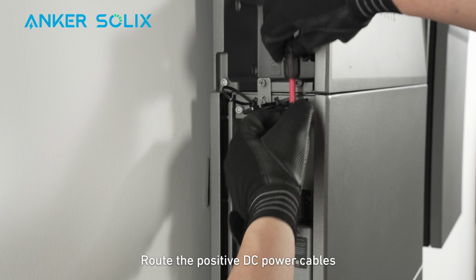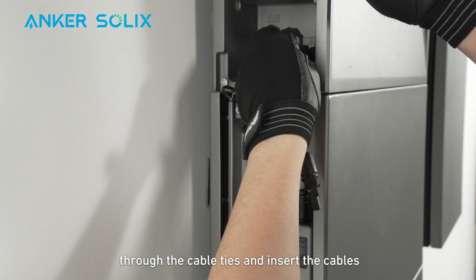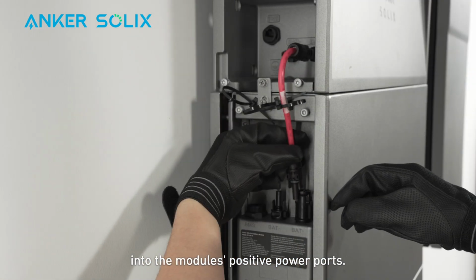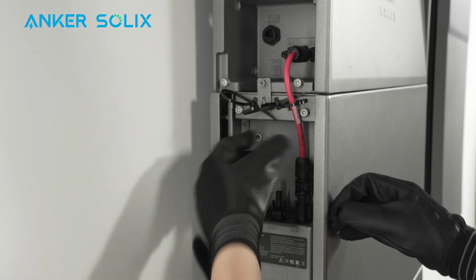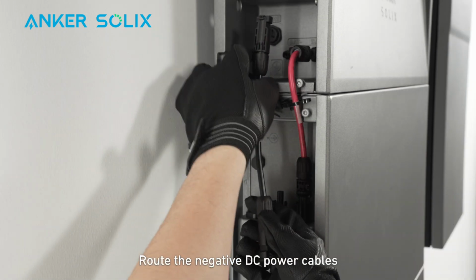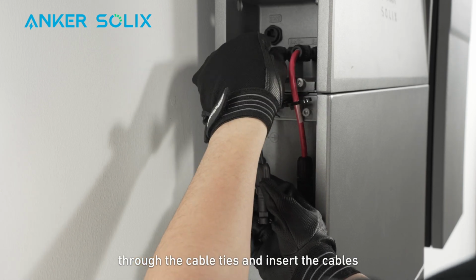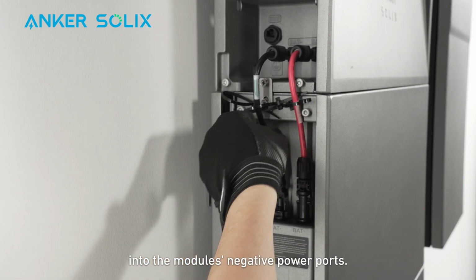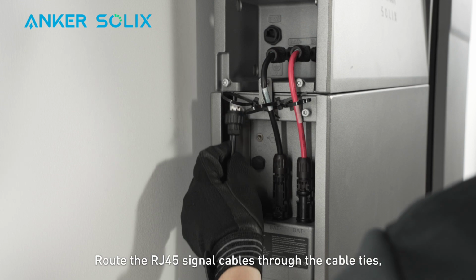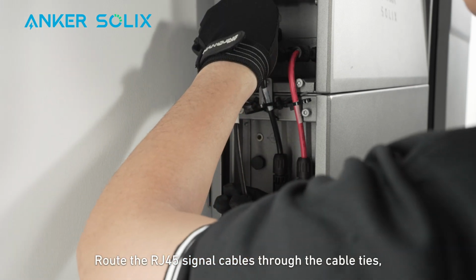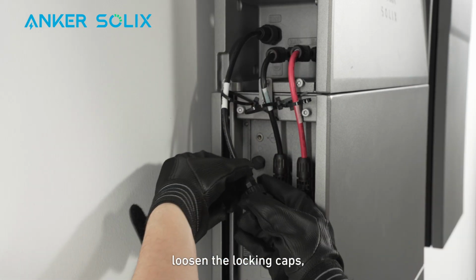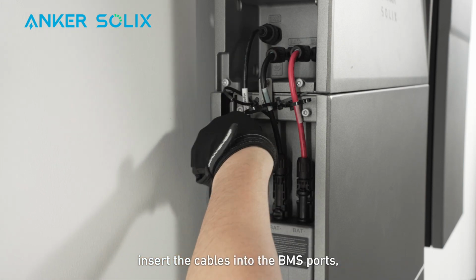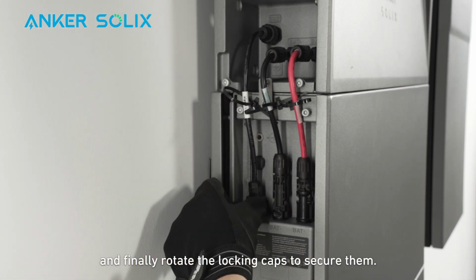Route the positive DC power cables through the cable ties and insert the cables into the module's positive power ports. Route the negative DC power cables through the cable ties and insert the cables into the module's negative power ports. Route the RJ45 signal cables through the cable ties. Loosen the locking caps, insert the cables into the BMS ports, and finally rotate the locking caps to secure them.